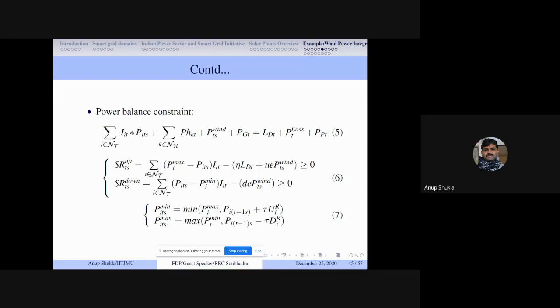When we talk about ramp up and down, let me explain: ramp up means if the generator is running at 100 megawatt and suddenly the load increases to some higher value, you cannot run that 100 megawatt directly to 500 megawatt. It cannot jump 400 megawatt in a certain time period because of its inertia and design. So there are certain ramp up limits. If a generator is running at 100 megawatt, it can only jump to 300 megawatt, so the ramp up rate is 200 megawatt. It is a percentage of the maximum rated capacity of the generator.